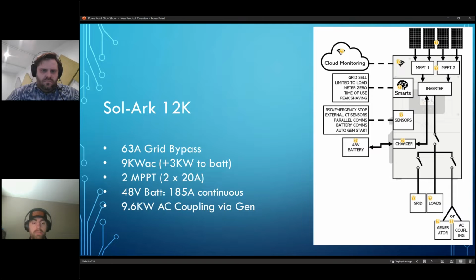So we're 48 volts battery nominal, 185 amps continuous charge and discharge. Going back to John's point, this limits the amount of charging time by charging at 1C rather than half, which really helps shorten that time period so you can get the most out of the AC part of the system.